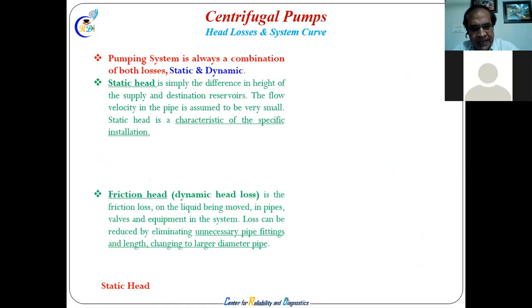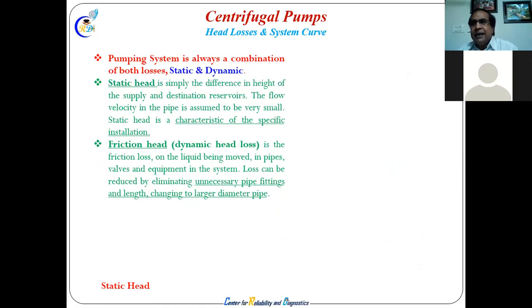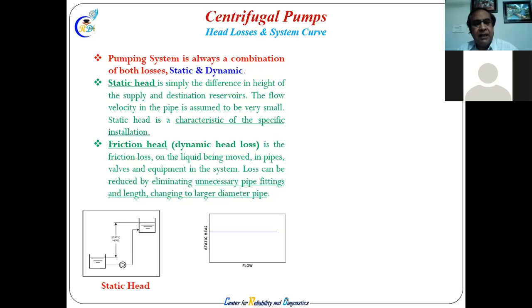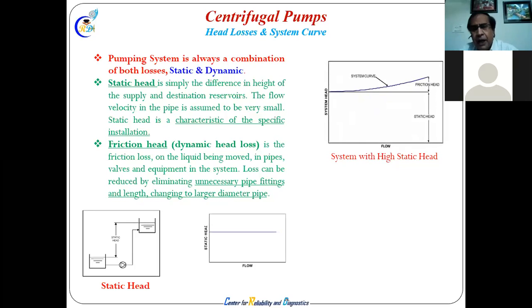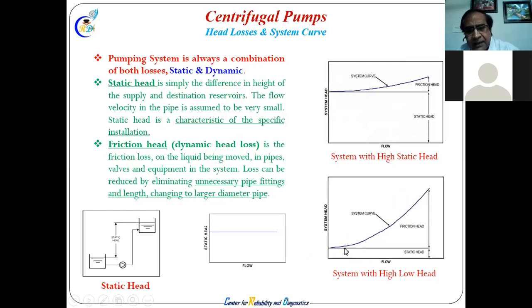So static head is a characteristic of the specific installation. How much up and down we are fitting the pump, the installation, is the static head. And friction head is the dynamic loss, the internal loss in the pipes. Okay, dynamic loss, and that gives us this type of curve. This is the system static head, how much height it is, and after that this is the friction dynamic head. Here static head is very less, dynamic is more. There are different ways of encountering this in energy savings.